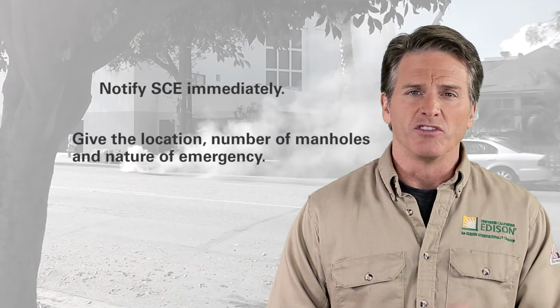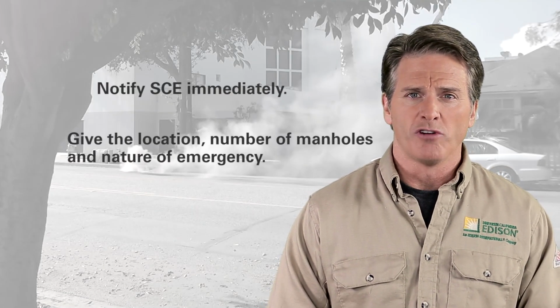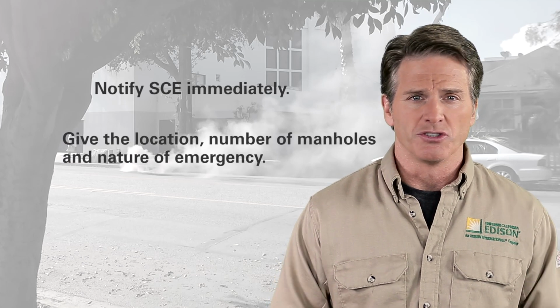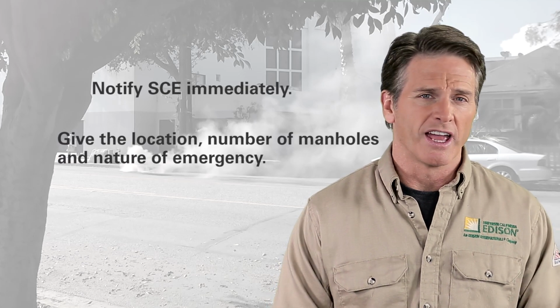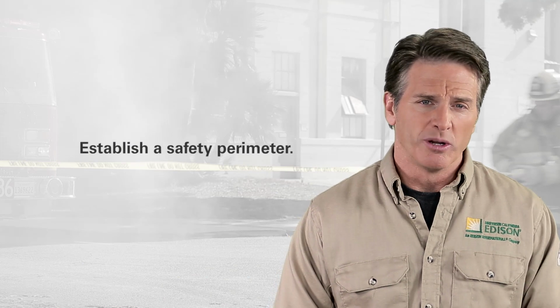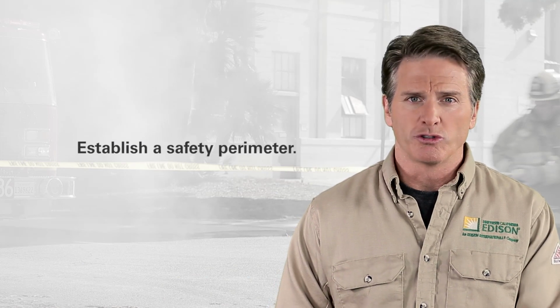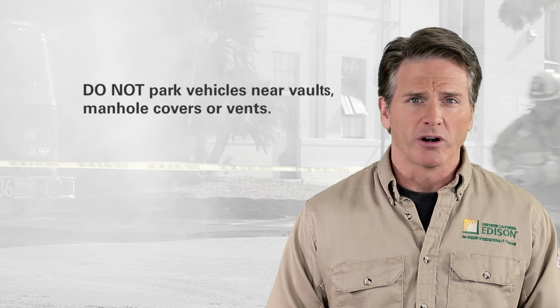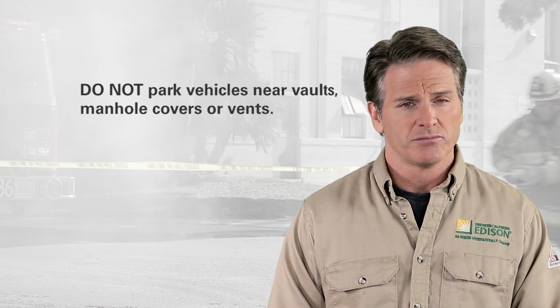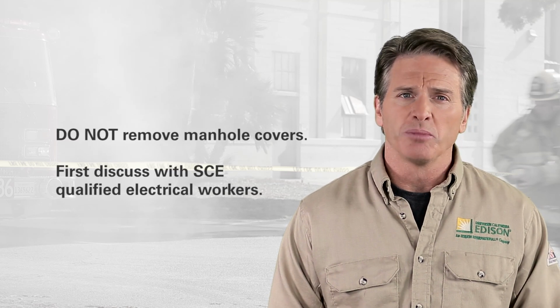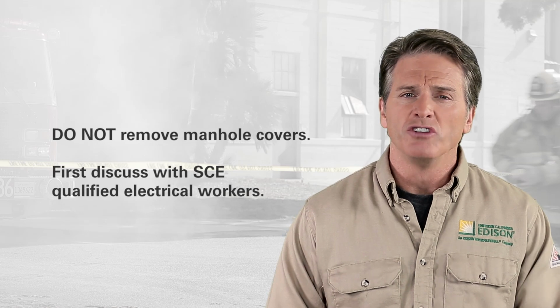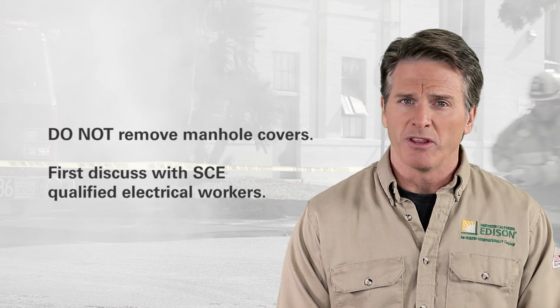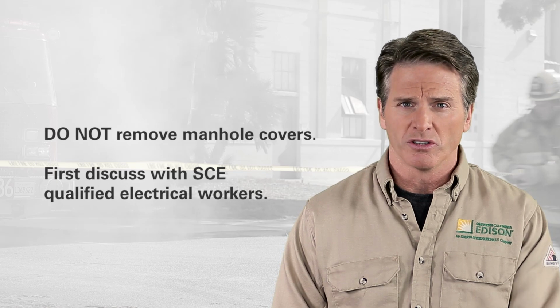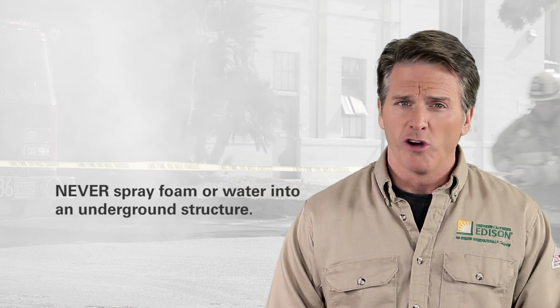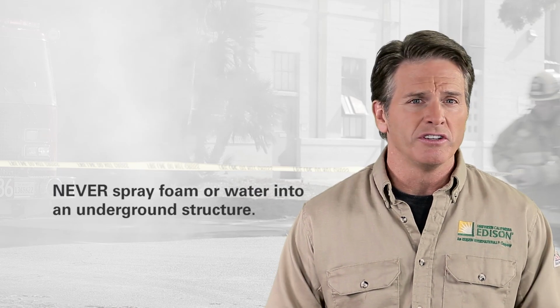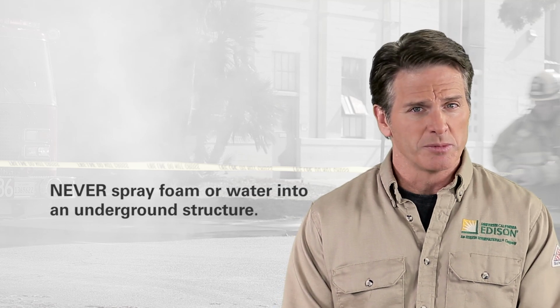Notify us. Give the location, number of manholes involved, and the nature of the emergency, such as flames, smoke, or the smell of gas. Establish a safety perimeter. Keep the public away and route traffic around the area. Don't park vehicles near vaults, manhole covers, or vents. If the cover is in place and smoke is coming from the holes in the cover, do not attempt to remove it until the conditions have been thoroughly discussed with our qualified utility workers. Never spray foam or water into an underground structure, even if a fire is visible, unless the structure has been de-energized.